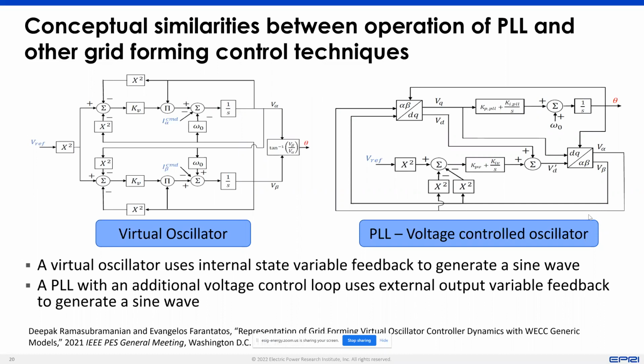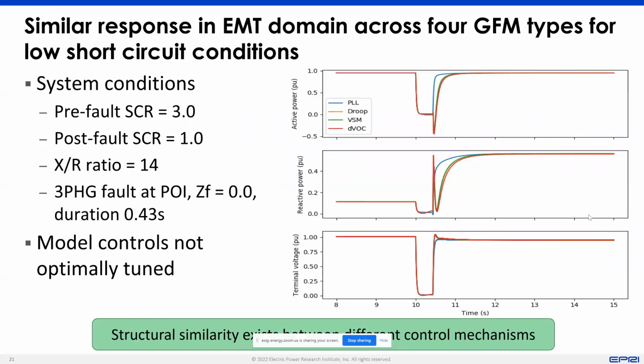So if we take the same concept and now we put it into an inverter, with all the current control loops and all the DC side regulation that we have, and we put it into a system, and we test it. And this was tested against one of the criteria that AEMO has for their model acceptance tests.